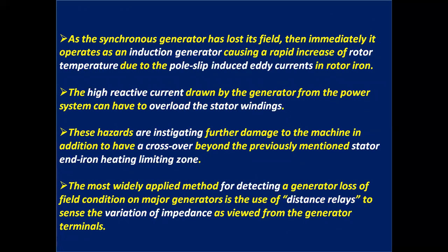As the synchronous generator has lost its field, it immediately operates as an induction generator, causing a rapid increase of rotor temperature due to the pole slip induced eddy currents in the rotor iron. The high reactive current drawn by the generator from the power system can overload the stator windings.